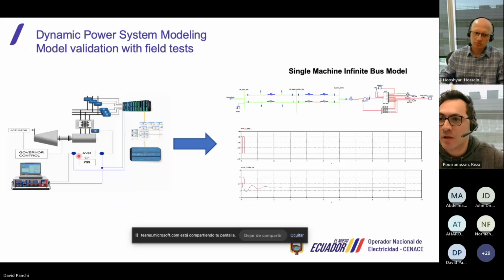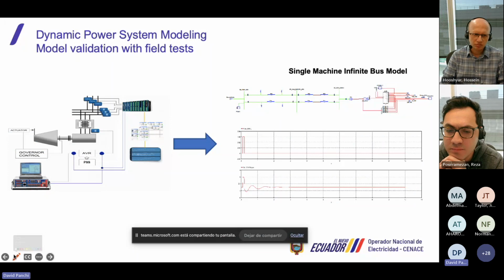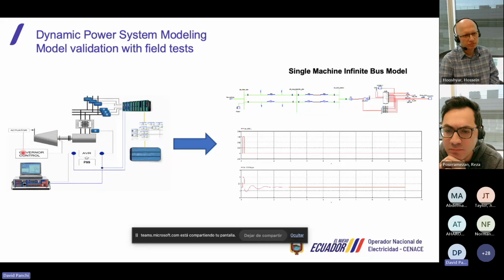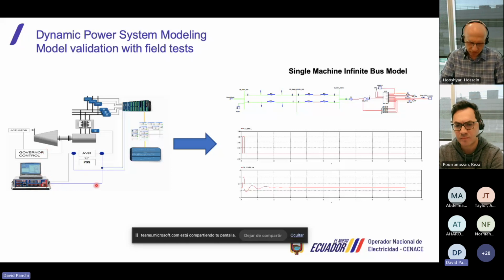Are you muted? So here in the presentation, in our methodology, we went to the field, to the power plant. We test the governor control, the AVR and PCS. We do several tests, like we inject with the Omicron a reference signal to the AVR. The same for the governor control. We send a reference and a step in the reference. With this step, we monitor the response of the governor, the AVR and the PSS in the WAMS system. We monitor and register all the data.